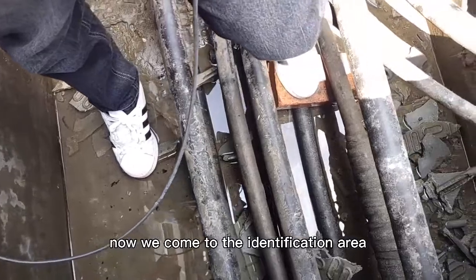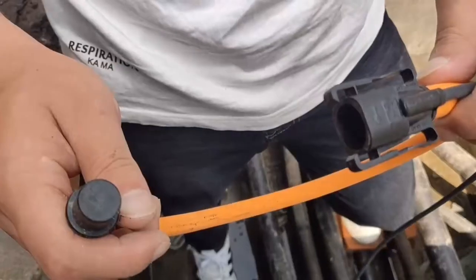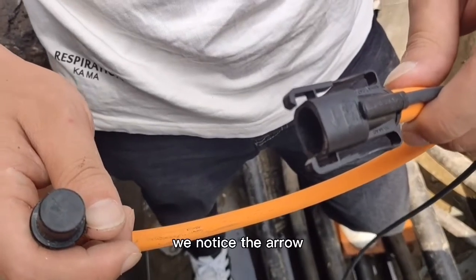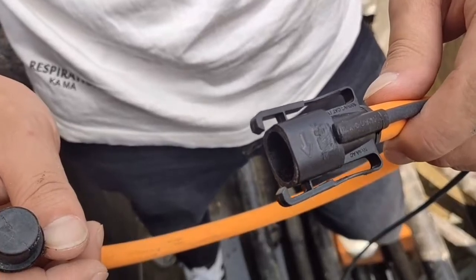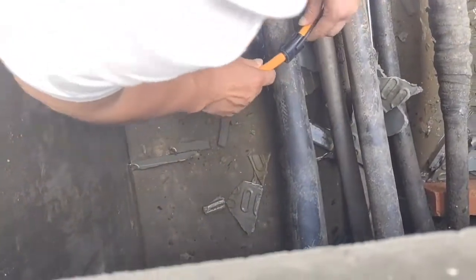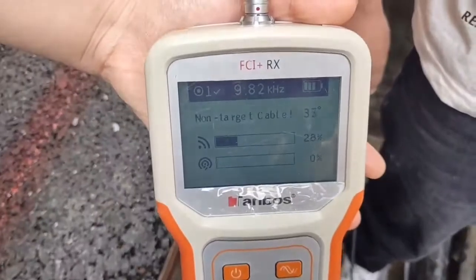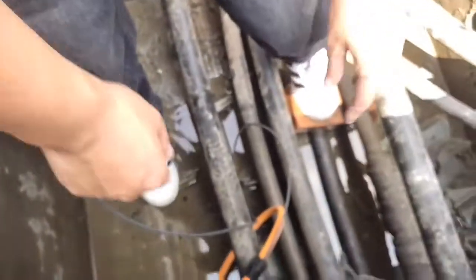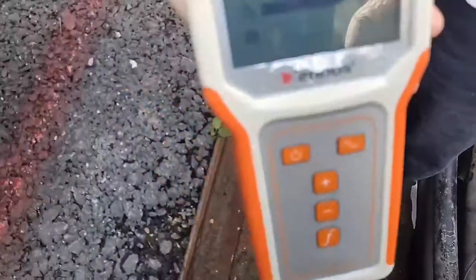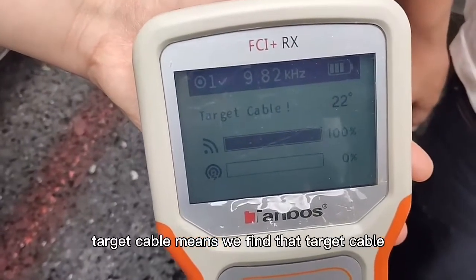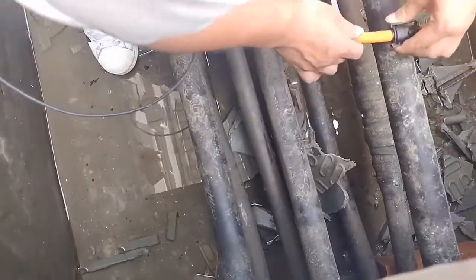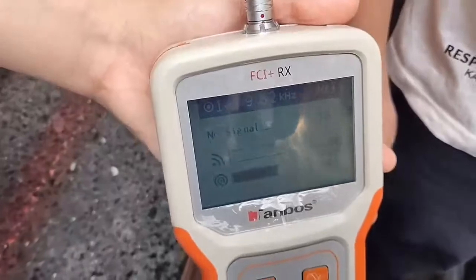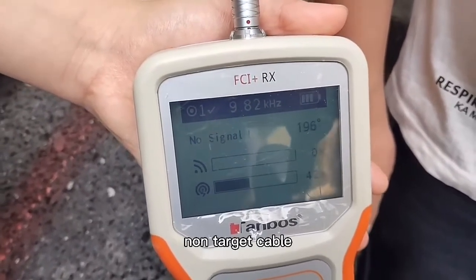Now we come to the identification area. We find many cables. Put the clamp on the cable. We notice the arrow must point to the far end of the cable, just like before. Non-target cable. Target cable means we find the target cable and then we try another. No signal. No signal means non-target cable.